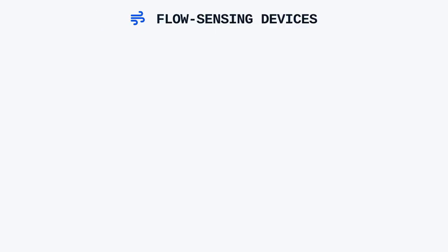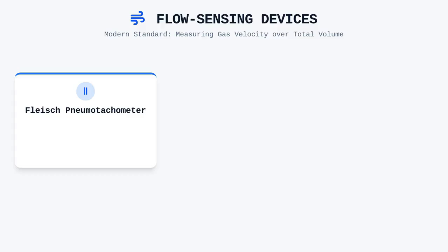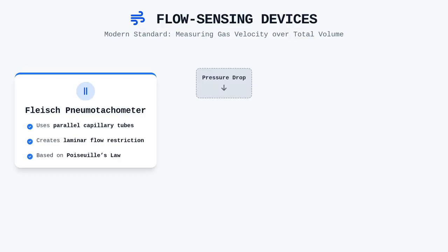Flow sensing devices, or pneumotachometers, represent the modern standard by measuring the velocity of gas rather than total volume. The Fleisch pneumotachometer operates on the principle of a resistive element, usually a series of small, parallel capillary tubes that create a laminar flow restriction. By measuring the pressure drop across this resistive element, the system calculates flow rate based on Poiseuille's law, which is then integrated over time to derive volume.